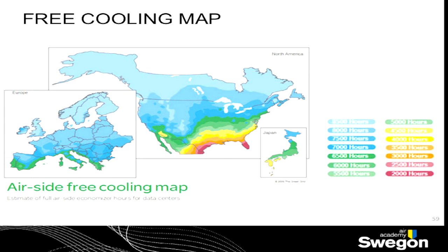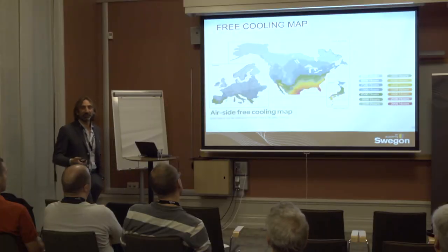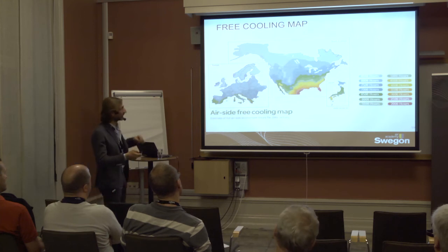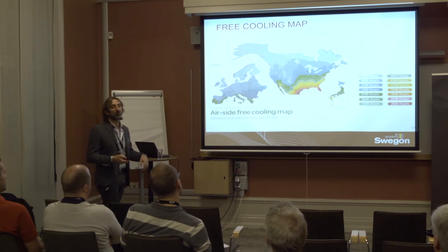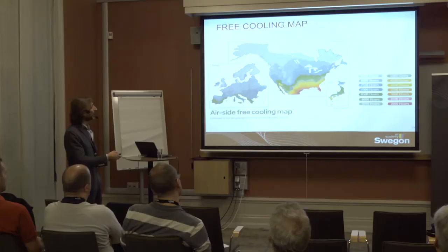So if you have got a direct free cooling system in the geographical area we considered, you can assume to have 7,000 to 7,500 free cooling hours per year. So mostly, more or less, let's say 80% of the total running time of the system, you can operate in direct free cooling. Of course, if you consider indirect free cooling, just due to the losses in the exchange between air and air, you lose something in terms of available hours. And this is the reason why we equip the system with an adiabatic cooling system, to increase the number of free cooling hours in a year.